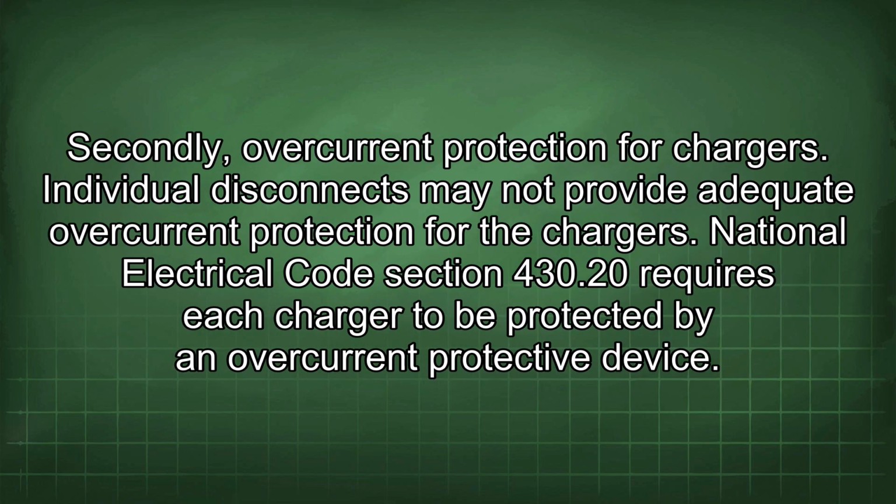Secondly, overcurrent protection for chargers. Individual disconnects may not provide adequate overcurrent protection for the chargers. National Electrical Code Section 430.20 requires each charger to be protected by an overcurrent protective device.